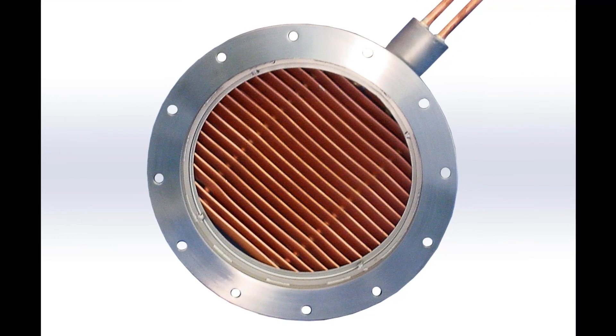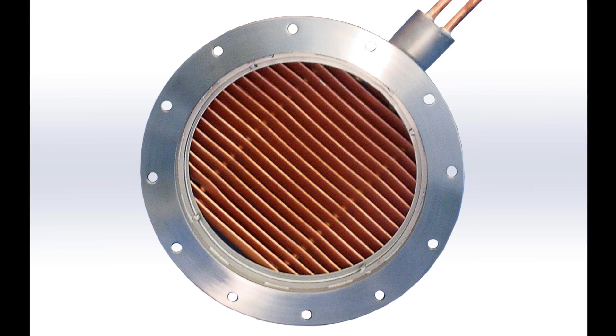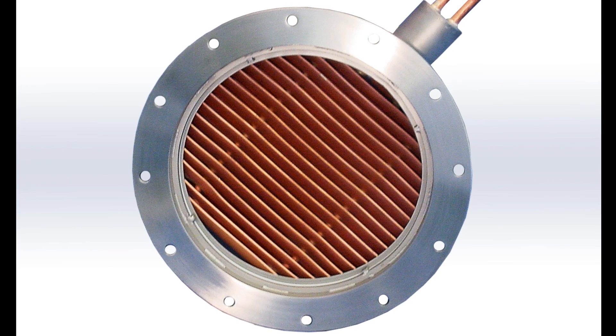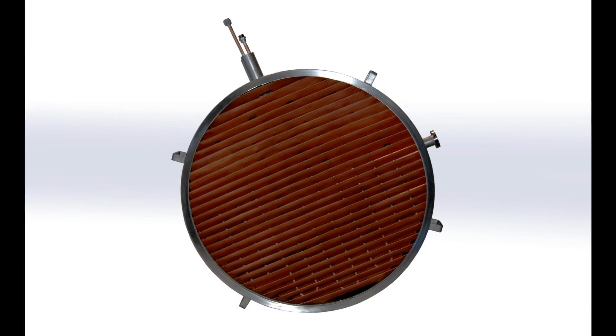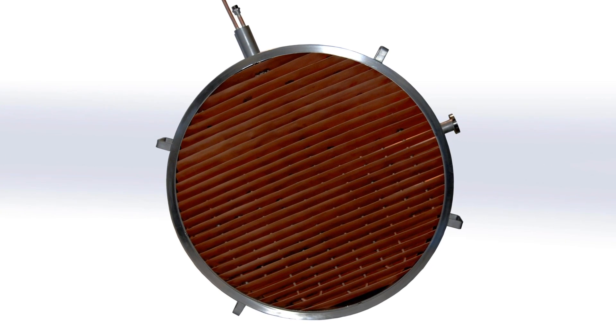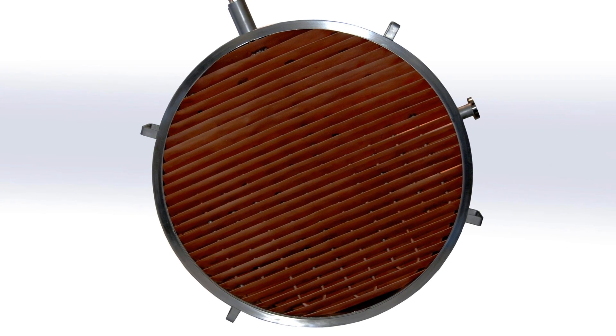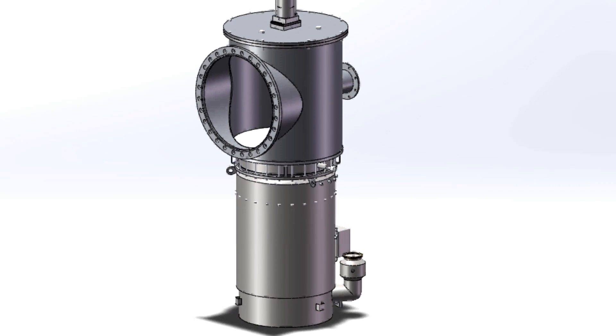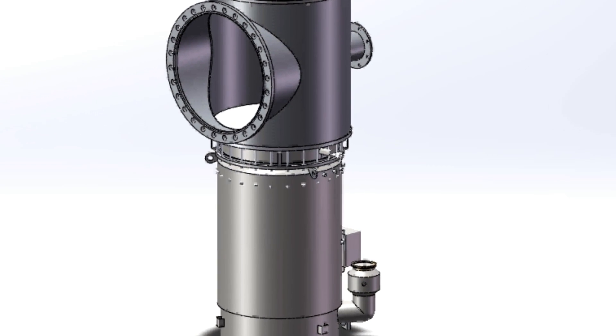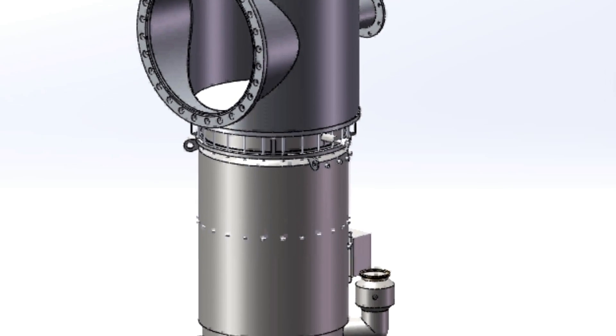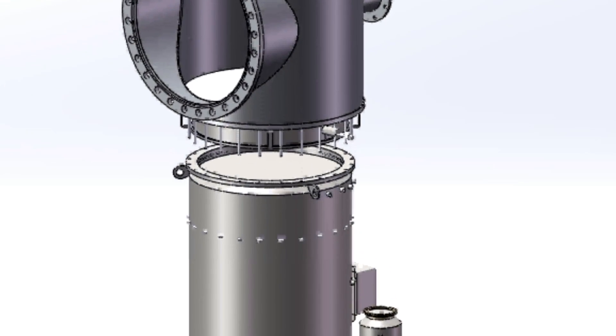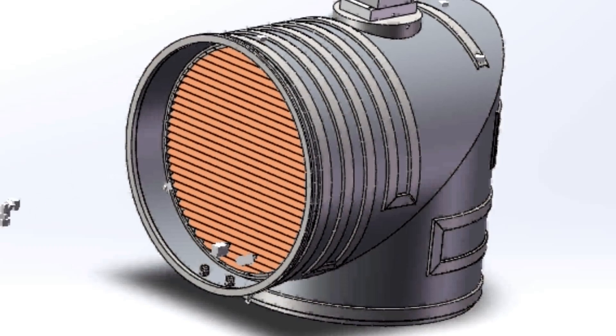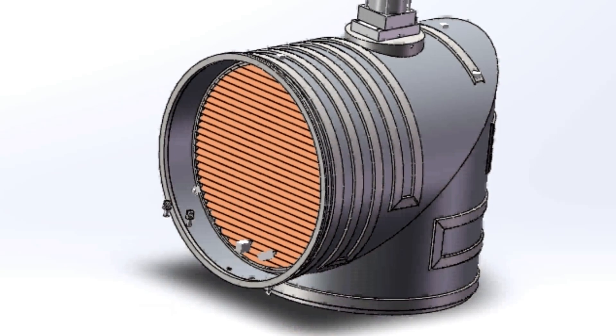For convenience, baffles come in numerous shapes. Some have flanges and are bolted to other flanged components. In other cases, the cost of the baffle can be reduced by eliminating the flanges and sandwiching it between two other flanged products — all that is required is to purchase extended-length mounting bolts. Some baffles are made to fit into a branch port and are installed from inside the chamber.